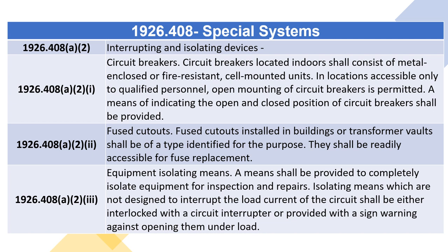Metallic enclosures shall be grounded. 1926.408(A)(2) — Interrupting and Isolating Devices. 1926.408(A)(2)(i) — Circuit Breakers. Circuit breakers located indoors shall consist of metal-enclosed or fire-resistant, cell-mounted units. In locations accessible only to qualified personnel, open mounting of circuit breakers is permitted. A means of indicating the open and closed position of circuit breakers shall be provided.